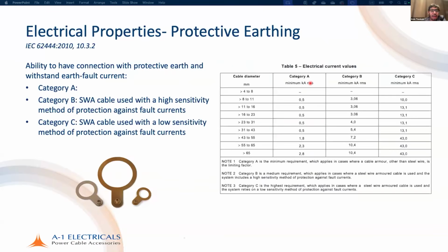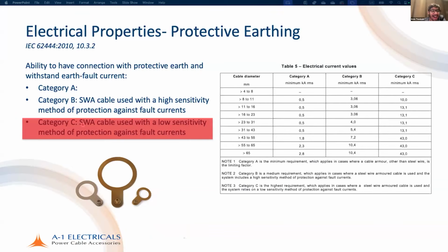In terms of the ability to withstand fault current, the earth tag is very, very important. There are three categories: category A, category B, category C. Like Mr. Gandhi is telling me, the A1 glands come under category C, which means the armored cable can be used with a low sensitivity method of protection against fault current. That may be, for example, an MCCB or an ACB. So very high amounts of fault current, right?